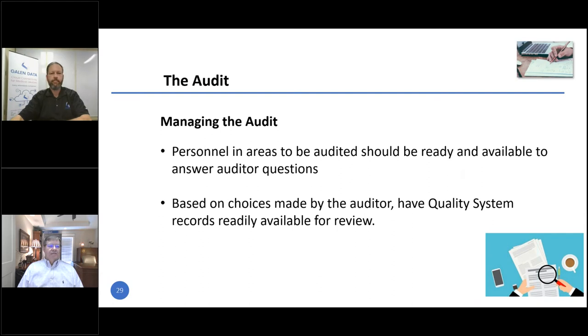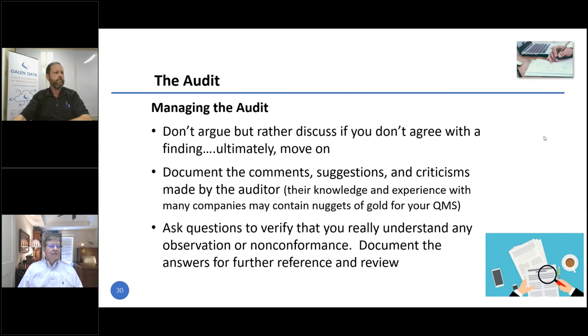Managing the audit: personnel need to be available to answer questions and have records available as soon as possible. Some things to remember: don't argue, discuss. If there's a nonconformance you don't agree with, you can discuss it, but take it and move on. Document the suggestions, comments, and criticisms of the auditor — there's gold in those comments. Ask questions to verify exactly what the auditor is saying, particularly in a nonconformance situation, so you understand specifically what their concern is.